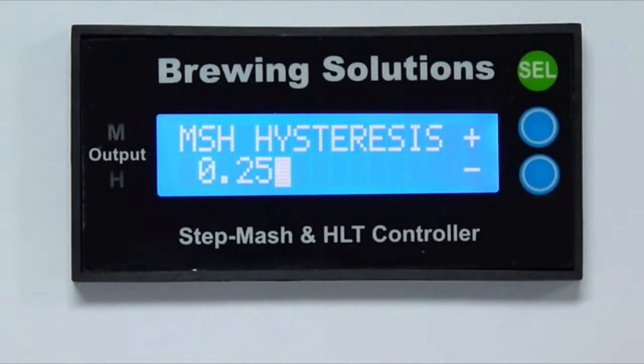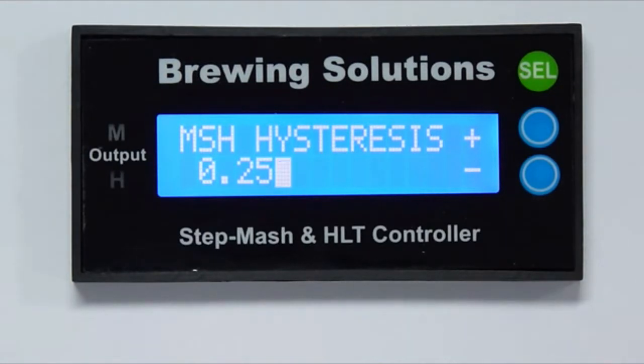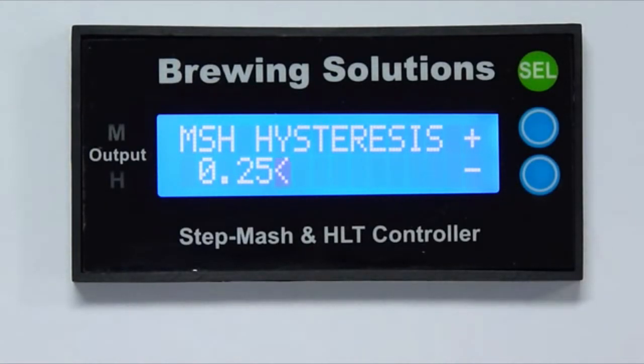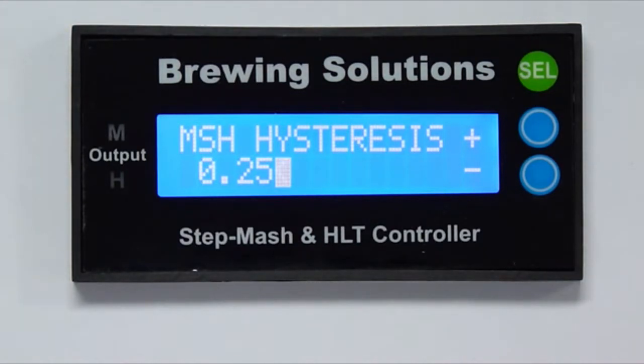For on-off selection, hysteresis will now display. 0.25 is the default setting for the controller. Hysteresis for this controller is single-sided operation. The control output will turn off when the desired set point is reached and will turn on when the temperature drops below the desired set point minus the hysteresis value. Hysteresis is adjustable in quarter degree increments from 0.25 to 1 for degrees Fahrenheit, and in eighth degree increments from 0.125 to 0.5 for degrees C.